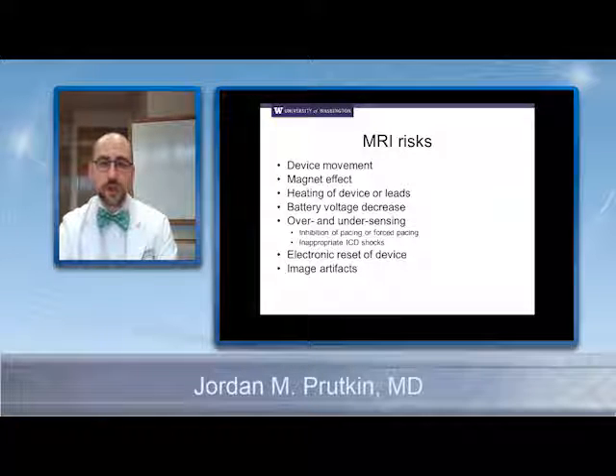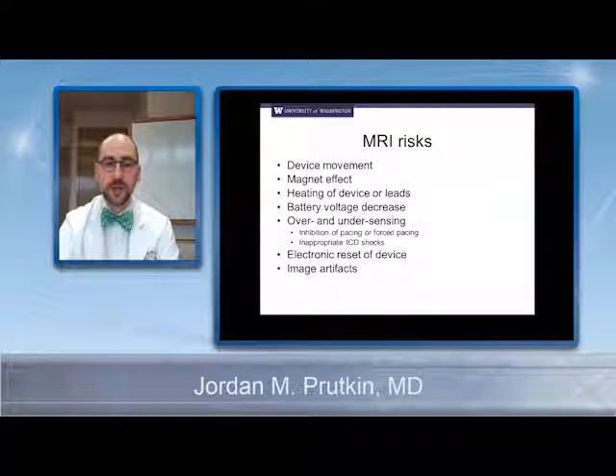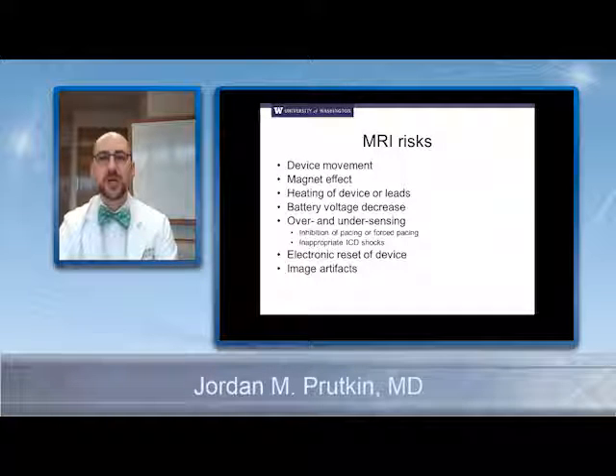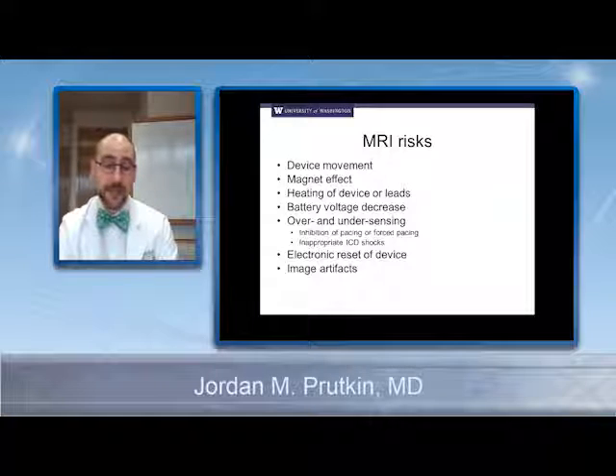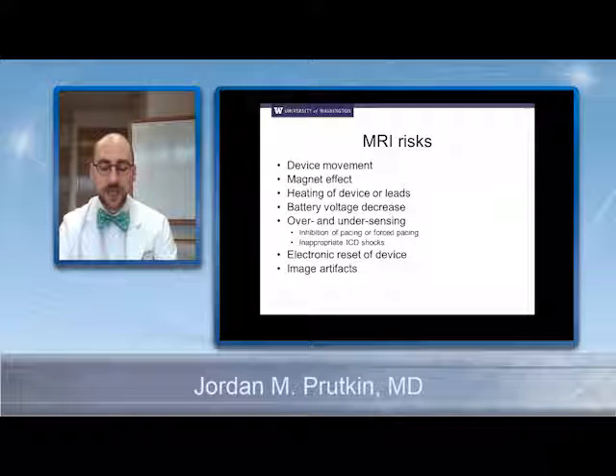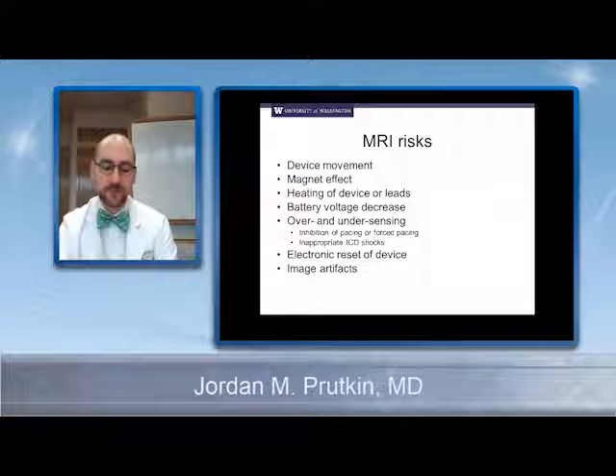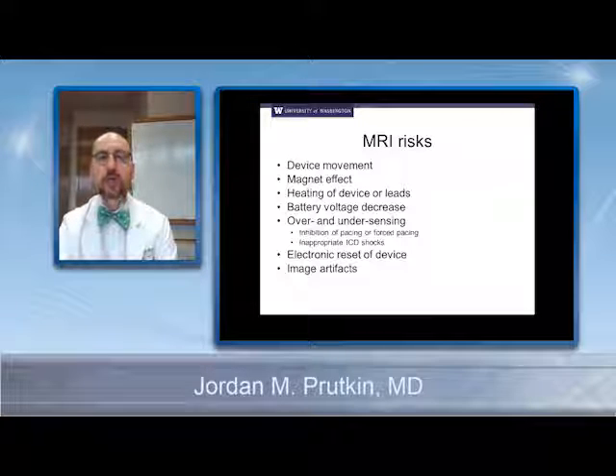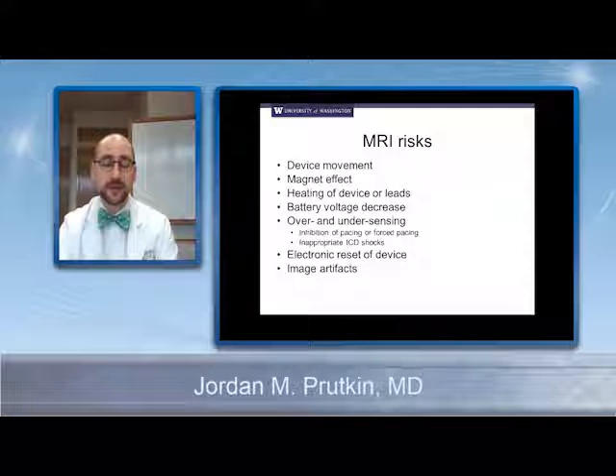With defibrillators, when you put a magnet on the device, it turns off the shock portion of the device and it has no effect on the pacing. So the concern when you get an MRI, which is a big magnet, is that magnet effect, or that it will trigger a magnet effect. And that is classically what had happened when the devices had a part of it called a reed switch in it, and they've switched now to a Hall sensor, so they're able to not have that be as big an issue. You can also get heating of the device or heating of the leads. So patients may talk about when they get an MRI that they feel the device just a little bit warmer, a half a degree or a degree warmer. It's not really a significant issue. What is a little bit more of an issue in some situations would be heating of the leads.